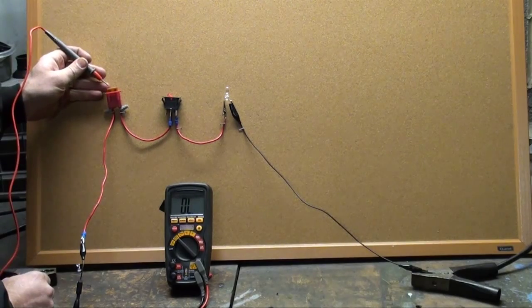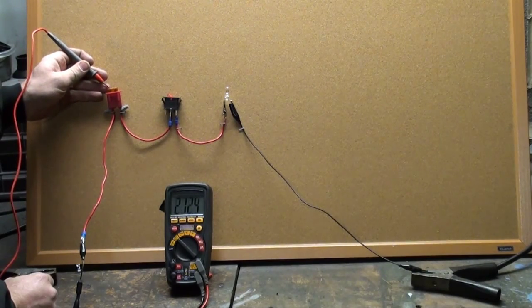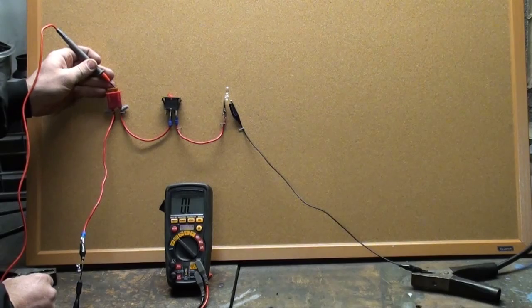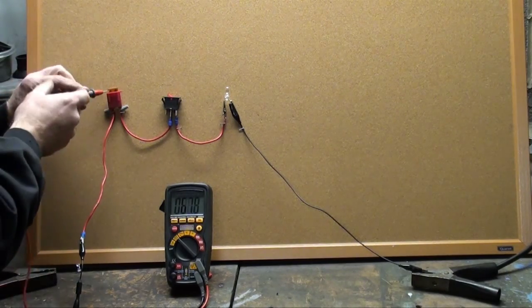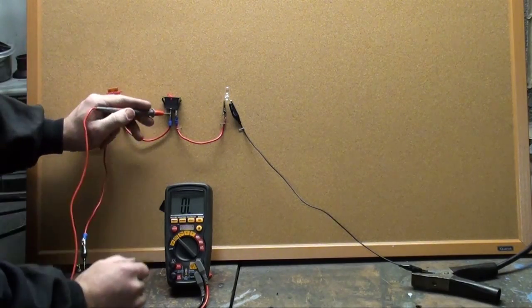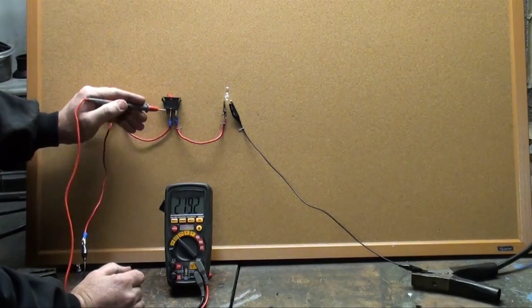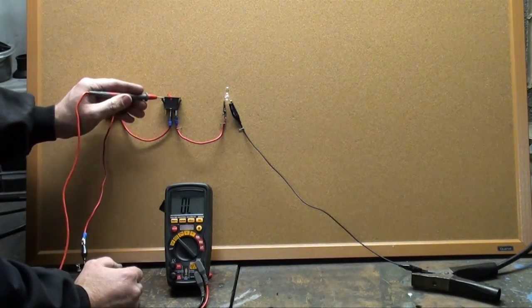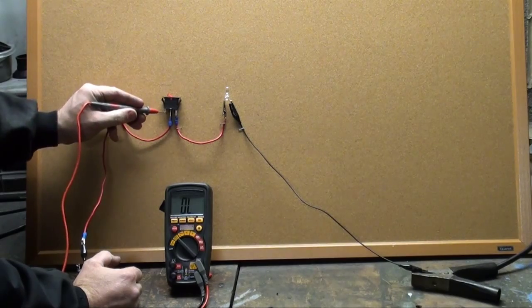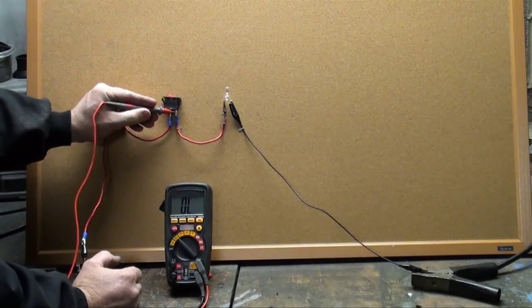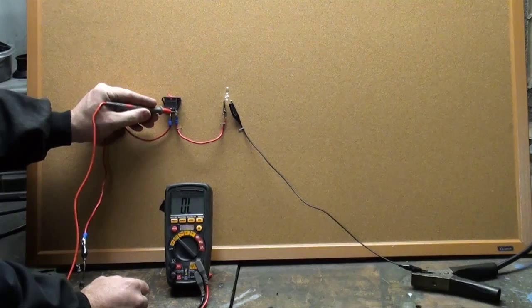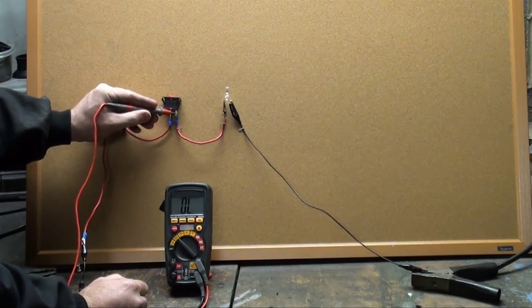It's good, the circuit's good to that side of the fuse. It's good on that side of the fuse. So we come down around. The circuit's complete to that side of the single pole, single throw switch. Come over to the other side of the switch. I have no continuity, so the circuit's not continuous to that point.